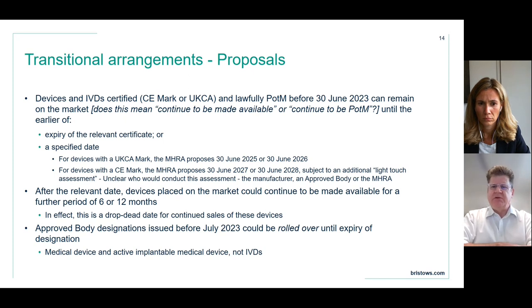It's worth noting that the majority of MDD certificates, so certificates under the directive, are likely to expire in May 2024. So the provisions here that enable the holder of a CE mark to continue to place products on the market through to 2027 or 2028 are likely to only realistically be for products that have an MDR CE mark.